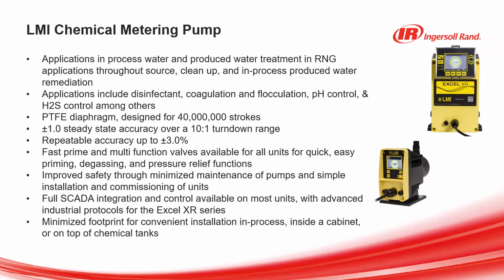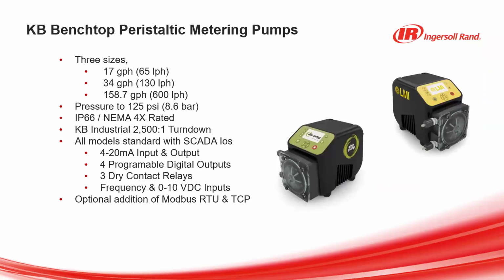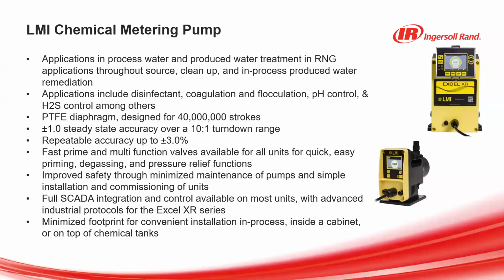One of the great advantages of a solenoid metering pump is it provides plus or minus 1% of steady state accuracy. As I said, there's fast prime and multifunction valves for inherent safety and easy commissioning of the pump, and full SCADA integration and industrial protocols as well.